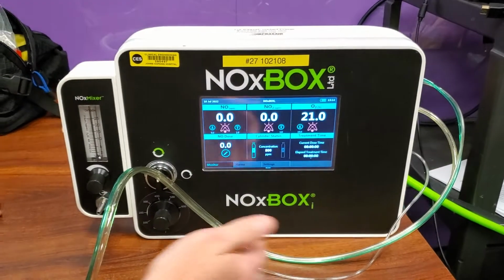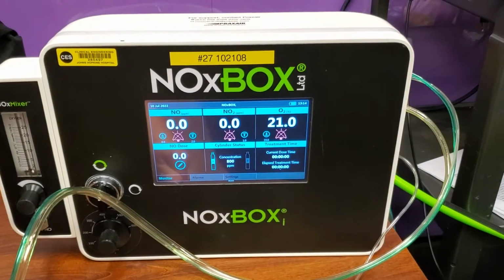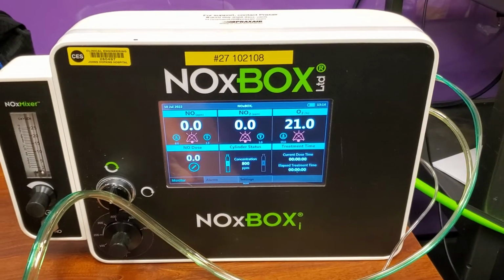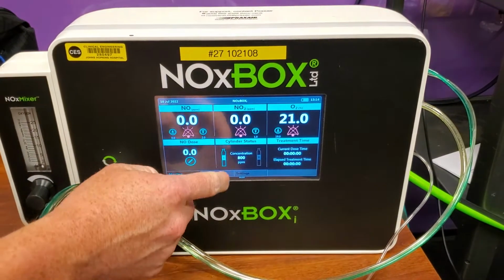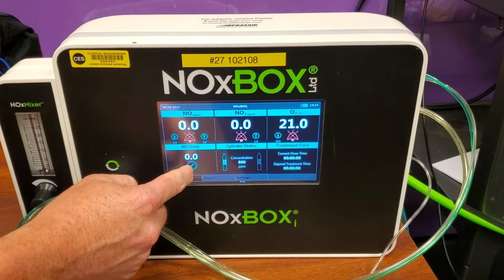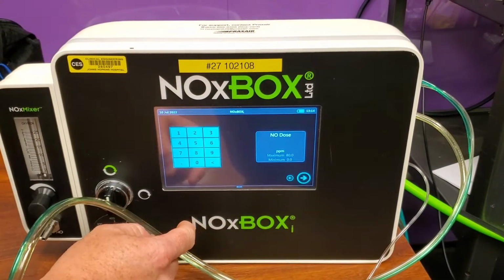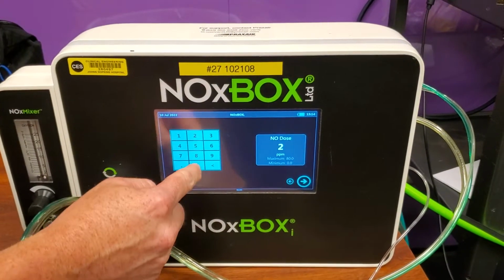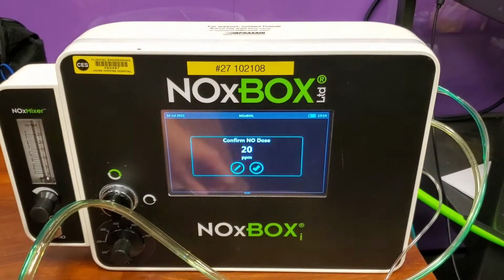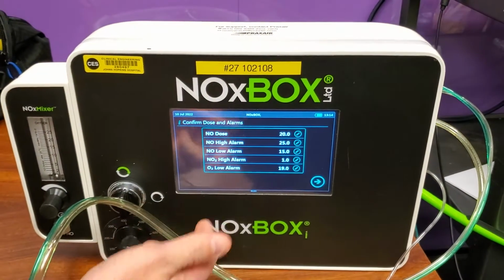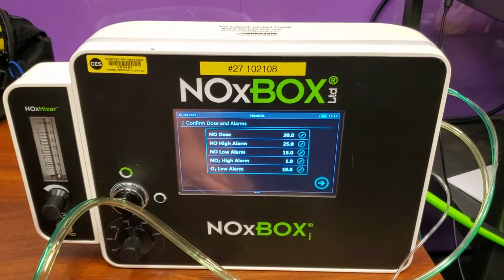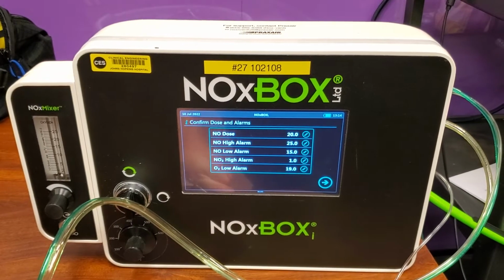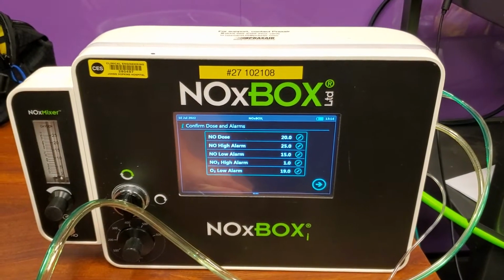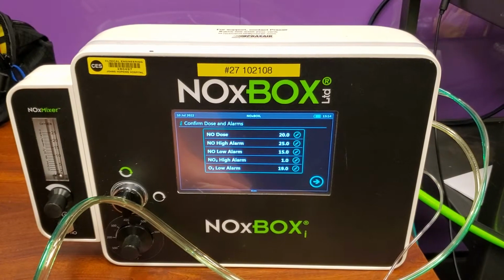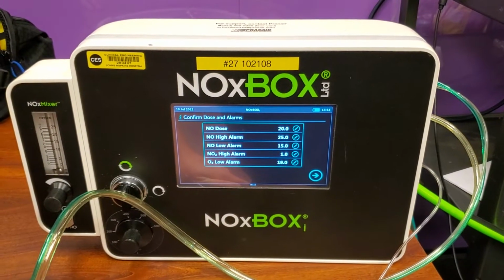Obviously, if you have the patient on 100%, it would be reading 100% if you had the patient going through at this point. If we want to change our NO dose, we just click on this small little pencil here, and it would prompt us, say we wanted to put them on 20. Prompt us here. Going to confirm. As I mentioned, it'll make you confirm your alarms here. You can change your alarms if necessary, but we usually recommend using the manufacturer ones. That way, it will notify you if it sees anything 5 above, 5 below.